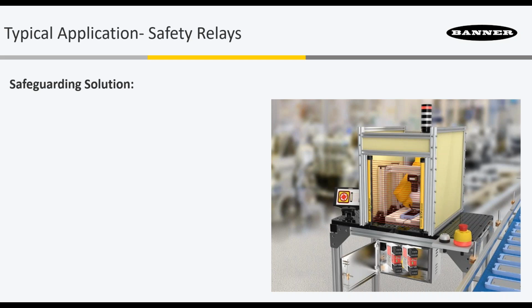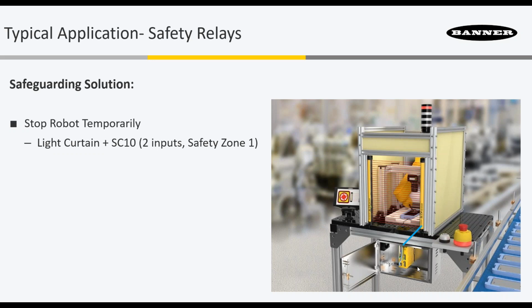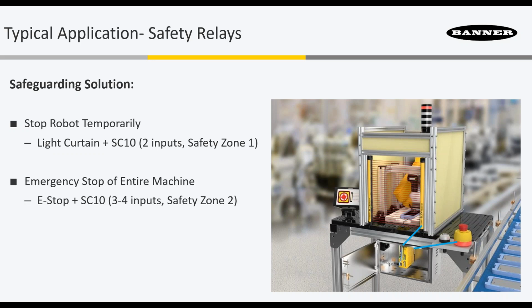So if you go back to this same machine, we introduced the SC10 that you saw on this just over a year ago. And going back to that same machine, what we can do with the SC10 is we can take off those 2 relays and replace them with the SC10. The light curtain will take up 2 of the inputs, so that'll be tied to safety zone 1, that first 6 amp relay output. And then the E-stop goes into, and depending on the type of E-stop and what you're trying to achieve, it's going to use 3 to 4 more inputs and be tied to safety zone 2. So in this case, the worst case, you'd use 6 inputs of the 10 inputs on the SC10, so you'd have 4 left over for other stuff.